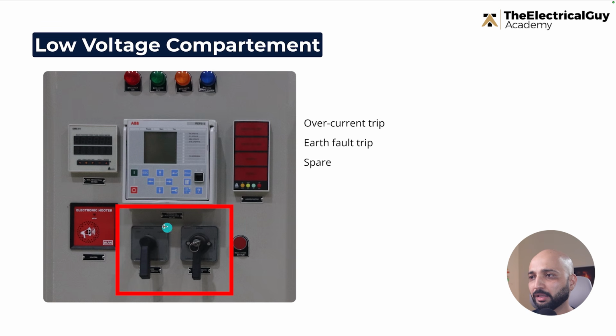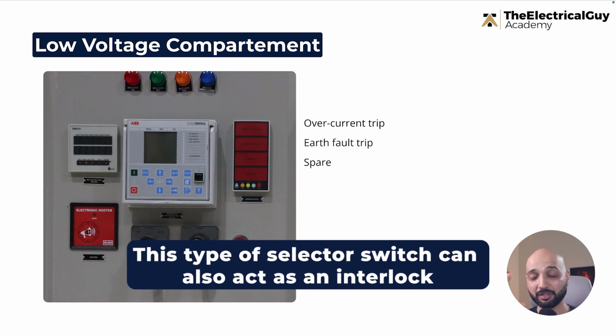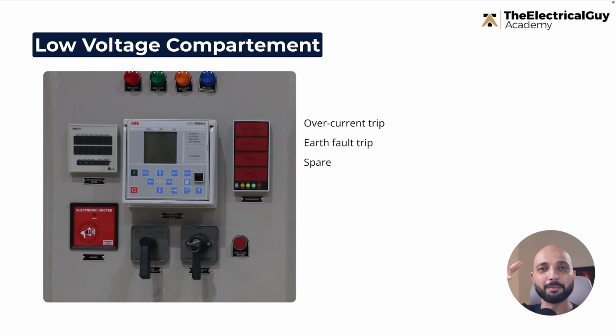Then first, you see there are 2 selector switches. The right one is basically the local and remote switch we talked about. When it's on the remote side, only remote operation is possible. Local is not possible. When it's on the local side, remote operation is not possible. So this also acts as an interlock. Imagine a situation, you're doing a local operation and someone also sends a command from the remote side. So there will be a chance of a worst condition. So to avoid such things, this also acts as an interlock. Only one side operation is possible. So that's one selector switch.